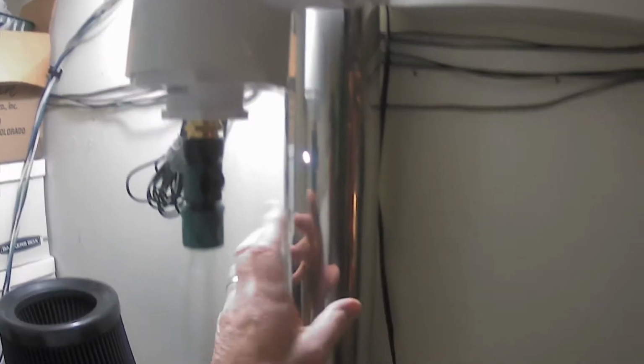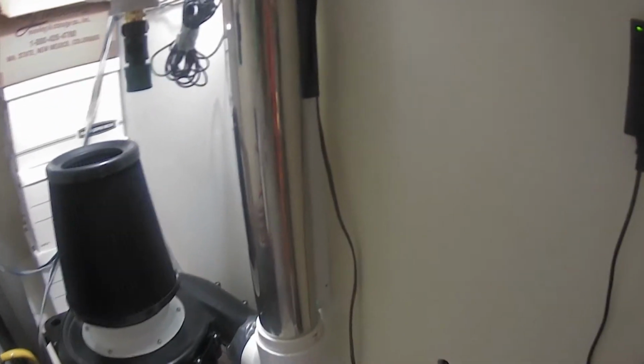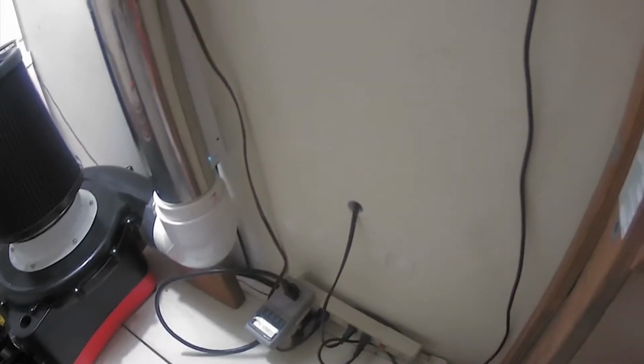Yep. Okay. So inside this thing, that's a 4-inch 304 stainless steel tube, 1/8 of an inch thick. And inside of it are two 3-foot germicidal lamps, 30 watts apiece. And they're creating a furnace, if you will, of UVC radiation in the neighborhood of about 15 millijoules. So all through this section of pipe, at any point, if you were to put a detector in that pipe, you would register 15 millijoules, which is actually quite a bit of UVC energy.